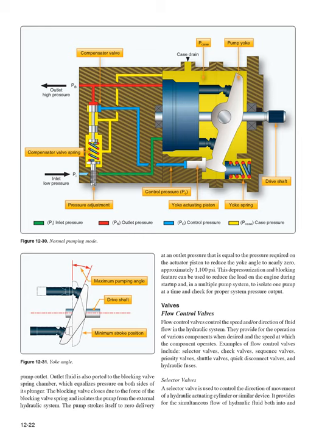Outlet fluid is also ported to the blocking valve spring chamber, which equalizes pressure on both sides of its plunger. The blocking valve closes due to the force of the blocking valve spring and isolates the pump from the external hydraulic system. The pump strokes itself to zero delivery at an outlet pressure that is equal to the pressure required for the actuator piston to reduce the yoke angle to nearly zero, approximately 1,100 pounds per square inch. This depressurization and blocking feature can be used to reduce the load on the engine during startup and, in a multiple pump system, to isolate one pump at a time and check for proper system pressure output.